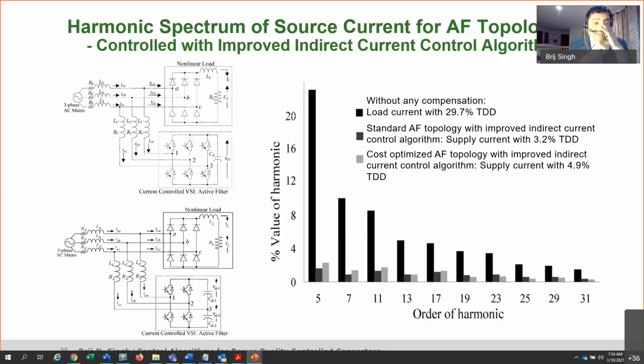Imagine there's a transformer feeding a colony, and somebody brought in a new refrigerator, or some novel electronic device, introducing a different type of harmonics. Then that passive filter will not be tuned. In addition, the tuning of these is load dependent. If the load is changing and deviating too much, you have to take care of the rest of it. So a combination of passive and active filter would be a good solution.